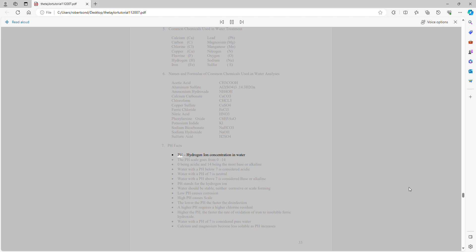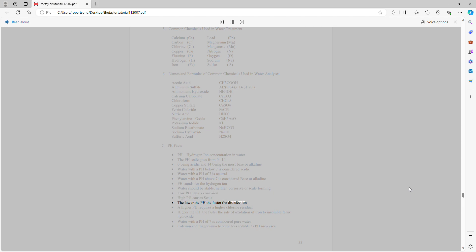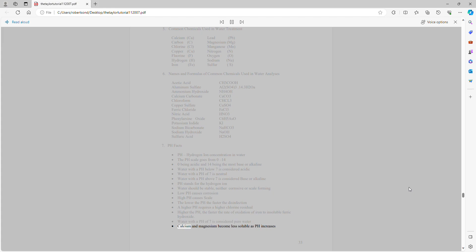pH facts: pH is the hydrogen ion concentration in water. The pH scale goes from 0 to 14 — 0 being acidic and 14 being the most base or alkaline. Water with a pH below 7 is acidic; pH of 7 is neutral; above 7 is base or alkaline. Water should be stable — neither corrosive nor scale-forming. Low pH causes corrosion; high pH causes scale. The lower the pH, the faster the disinfection. A higher pH requires a higher chlorine residual. Higher pH increases the rate of oxidation of iron to insoluble ferric hydroxide. Calcium and magnesium become less soluble as pH increases.